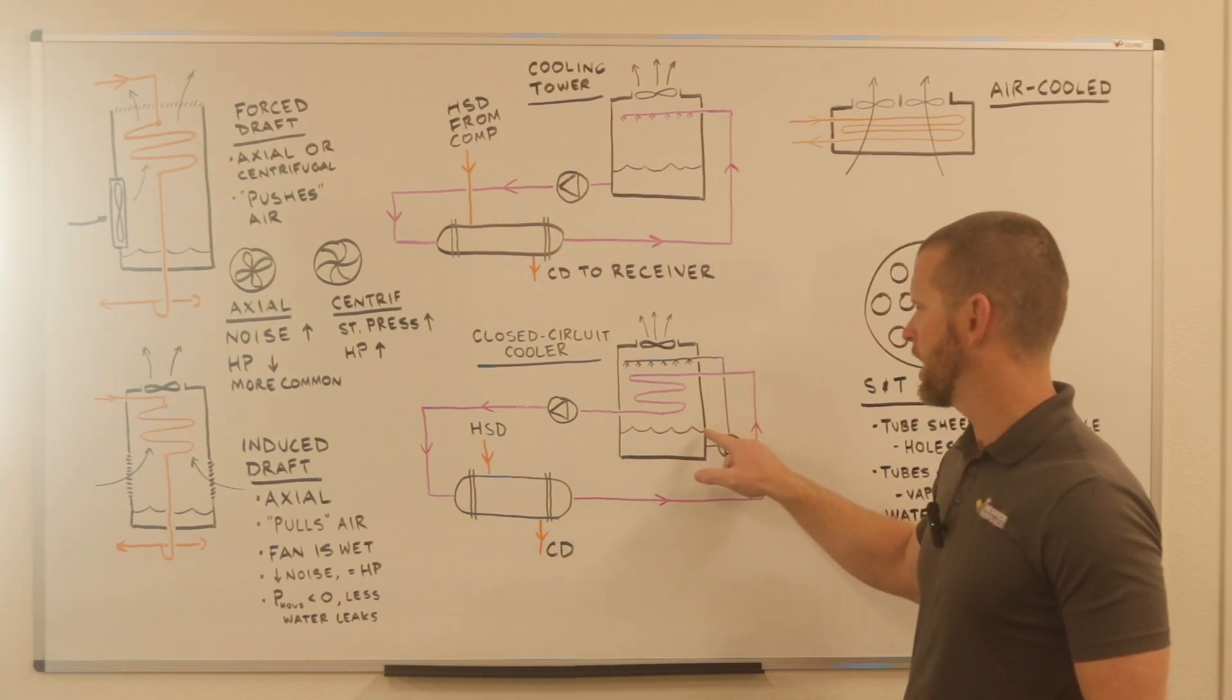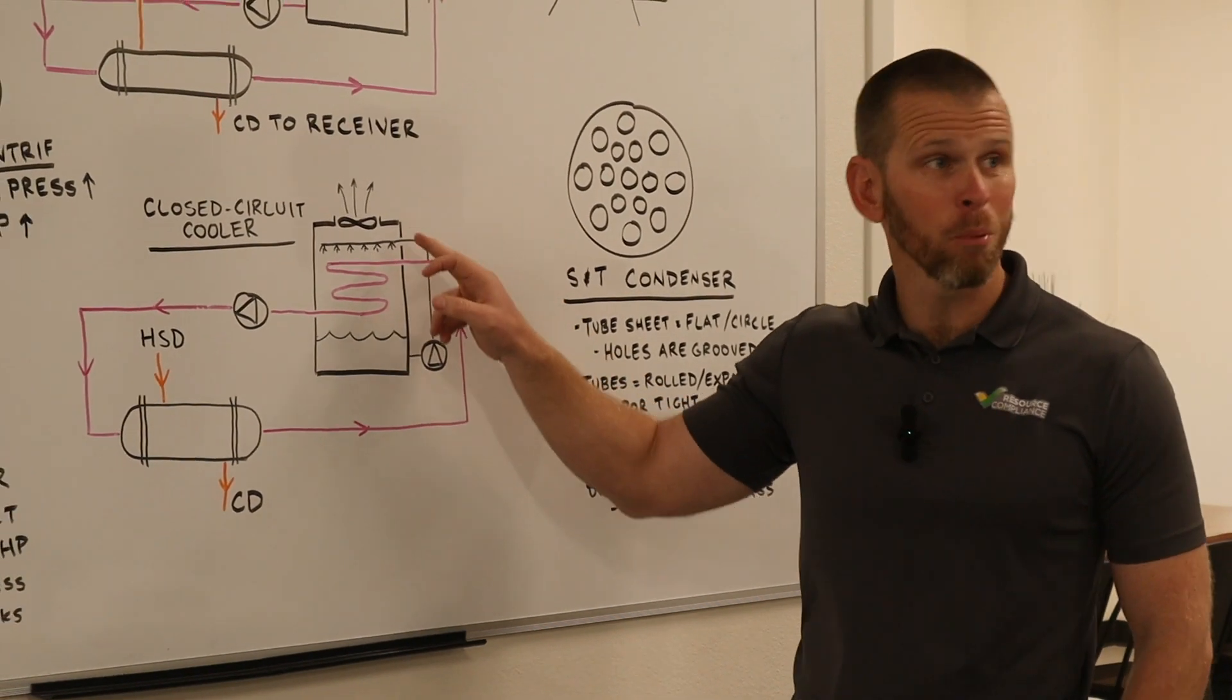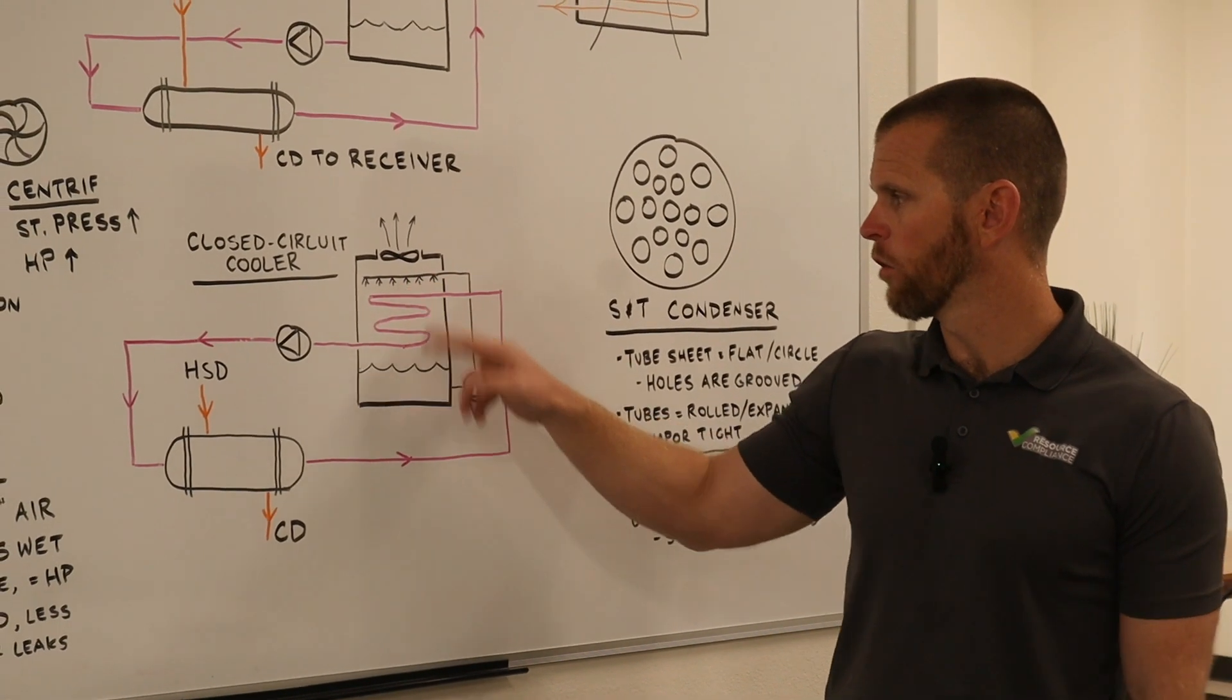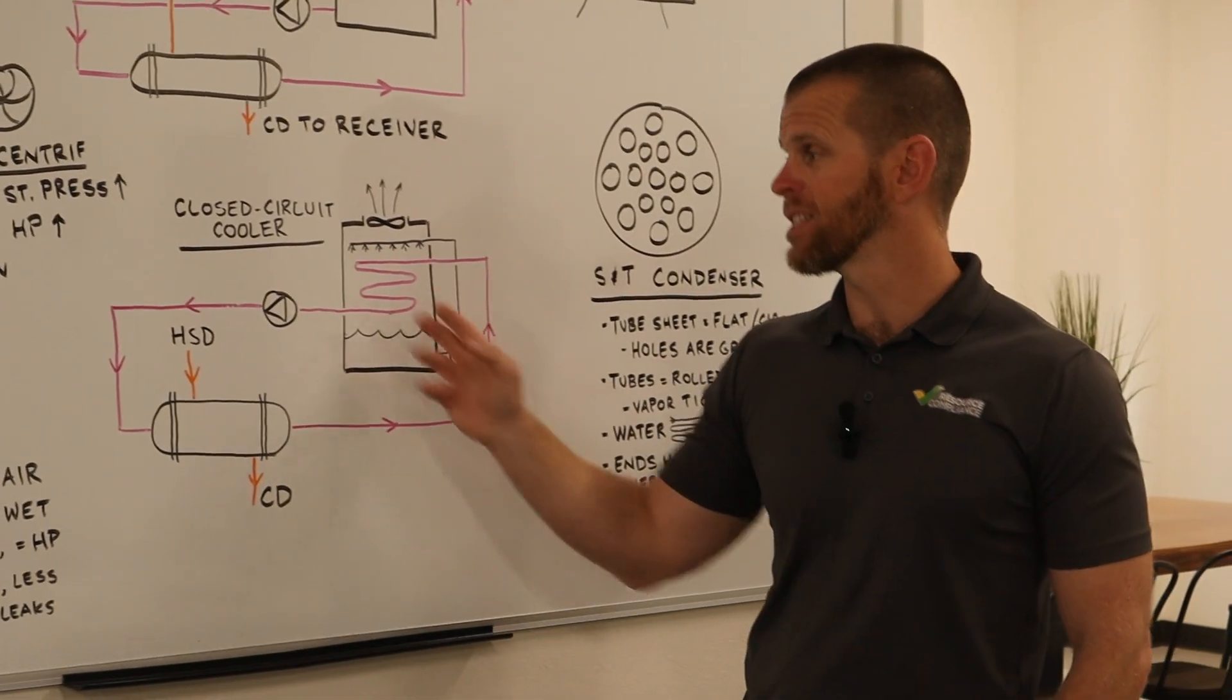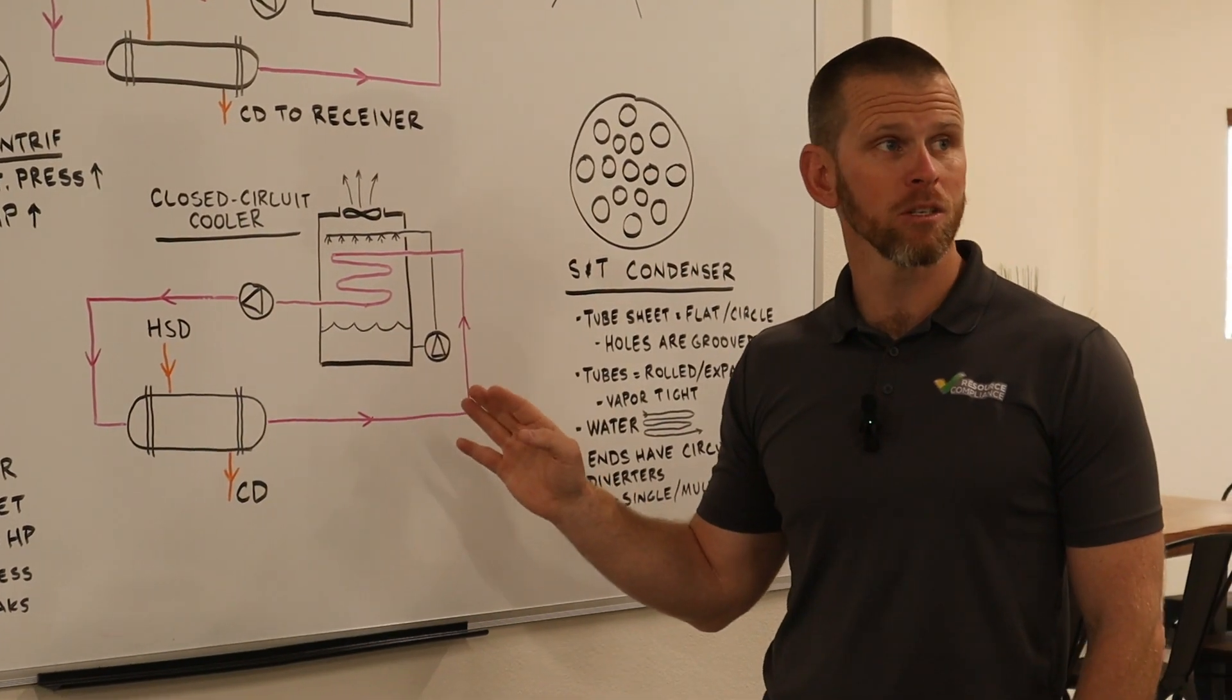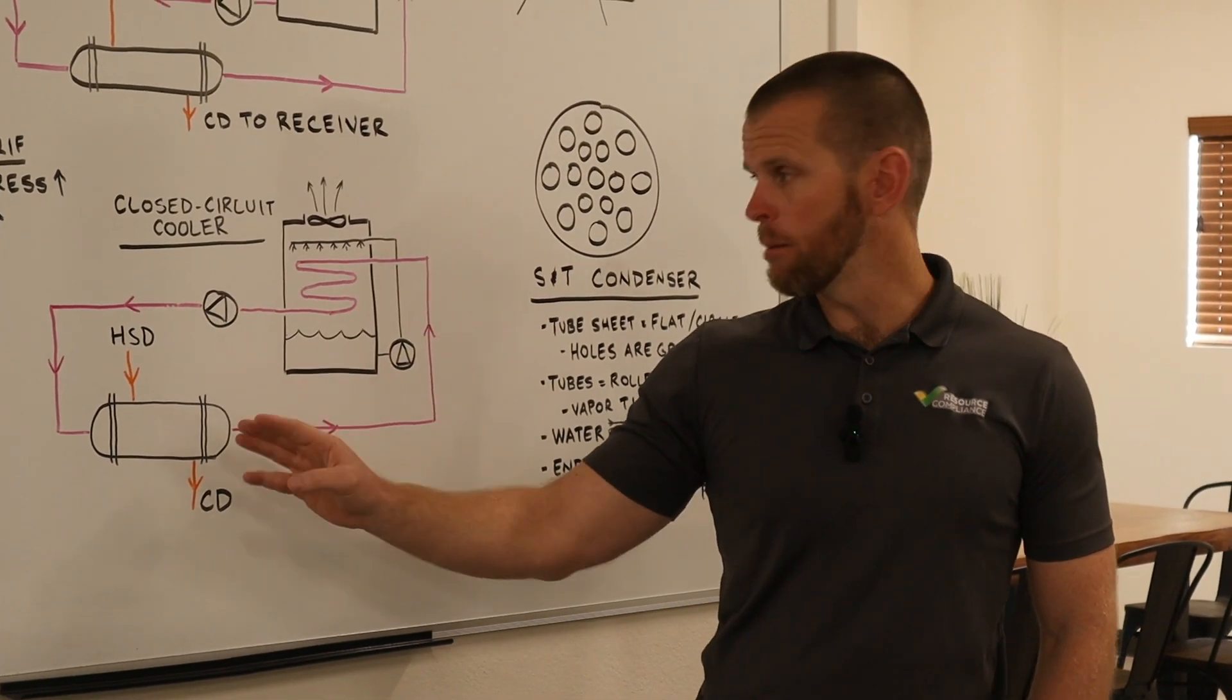We have a float that I didn't draw that would maintain a water level, and then water getting pumped through what I've drawn as a black pipe and sprayed over a tube bundle. Inside the tube bundle is our second circuit of water, which is the circuit that's flowing through our heat exchanger to desuperheat and condense the ammonia.